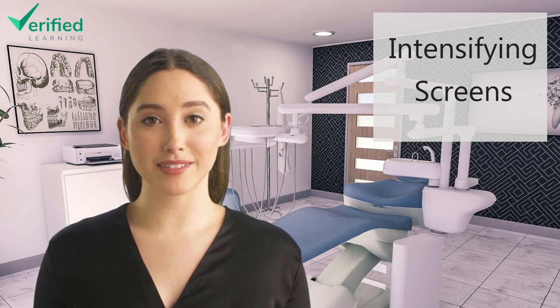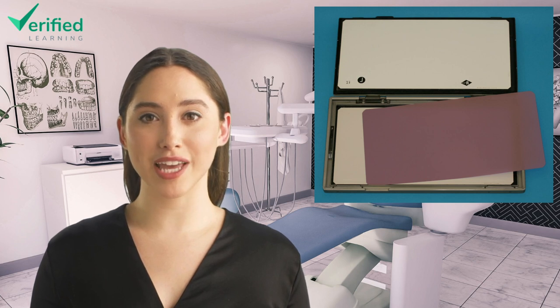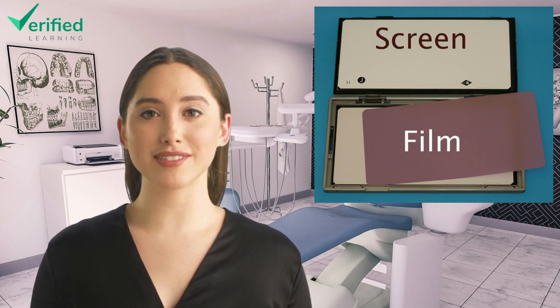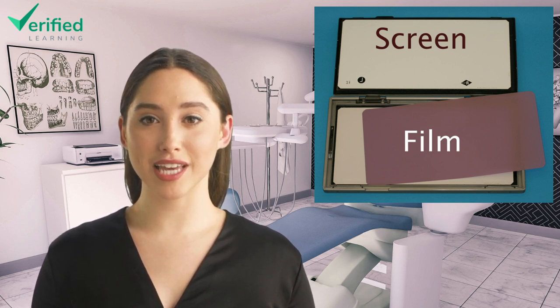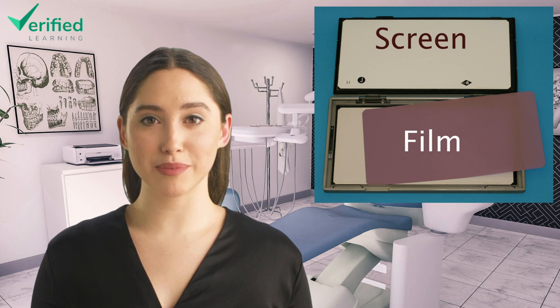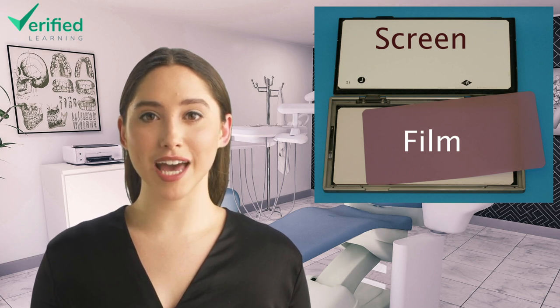They're not needed for digital PSP sensors. Those have a built-in phosphor layer that works in the same way. An intensifying screen is a sheet coated in crystals, called phosphors, which emit light when struck by x-rays. Intensifying screens absorb up to 40% of x-ray photons and turn them into light. When an intensifying screen is in contact with the film, an image is formed not only with the x-rays that trigger the film, but also by the light emitted by the screen. This effectively halves the dose of radiation needed to form an image.